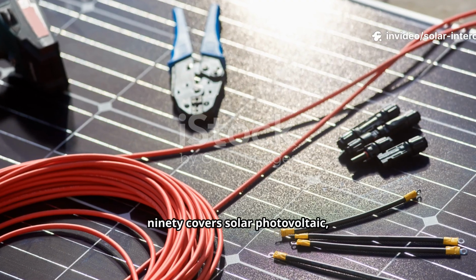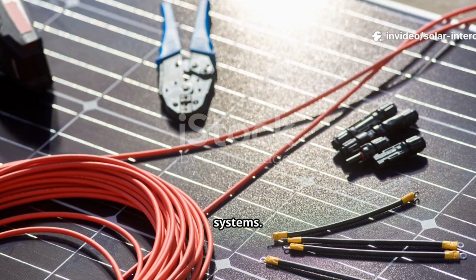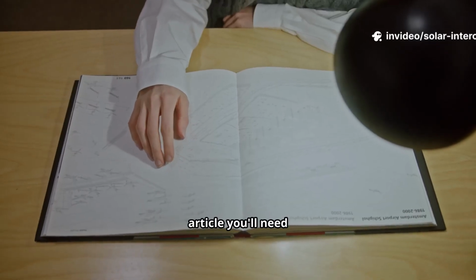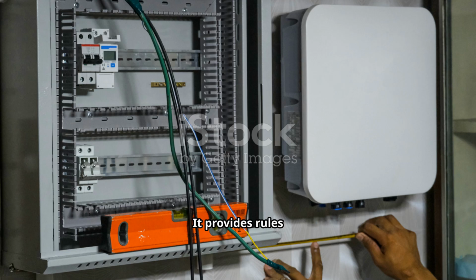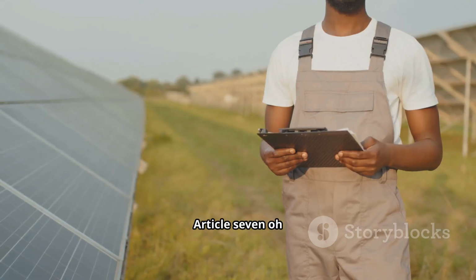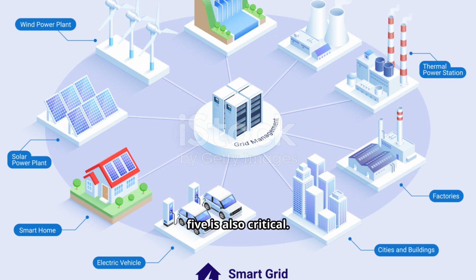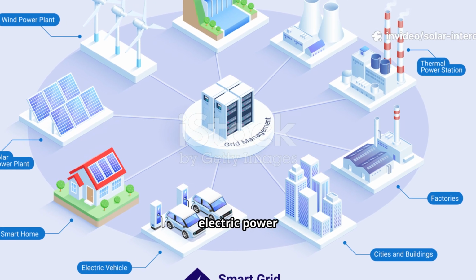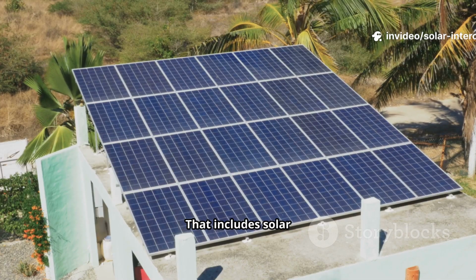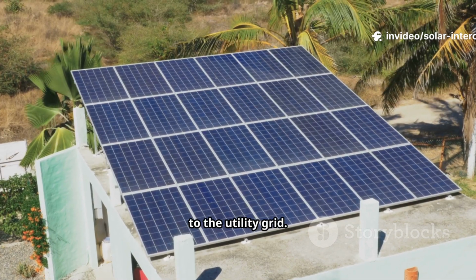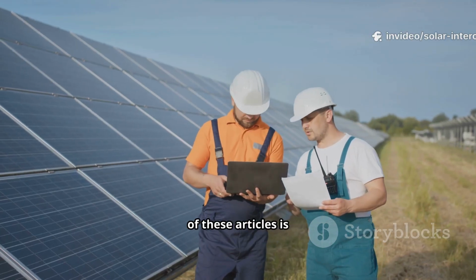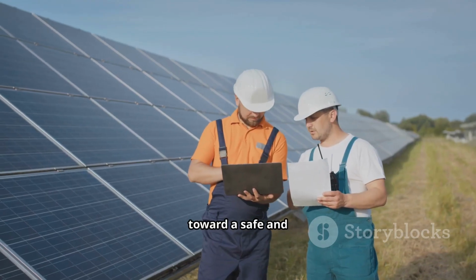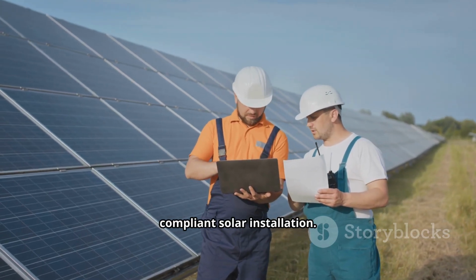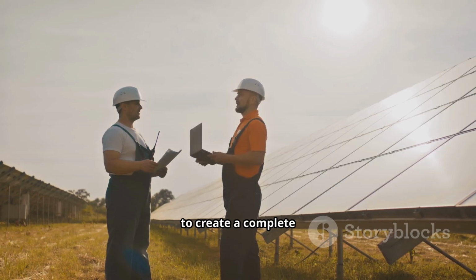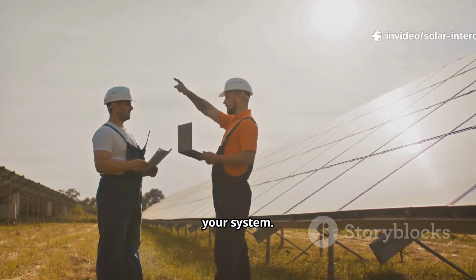NEC Article 690 covers solar photovoltaic or PV systems. This is the main article you'll need to know. It provides rules for wiring. It provides rules for inverters. Article 705 is also critical. It deals with interconnected electric power production sources. That includes solar systems that connect to the utility grid. Understanding both of these articles is the first step toward a safe and compliant solar installation. They work together to create a complete picture of the requirements for your system.